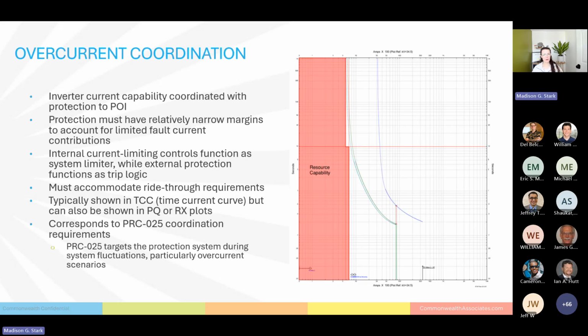The second part of this for inverters is the overcurrent coordination. The big thing that we want to see generally at POI again is that the protection system is not impeding the resource output capability. So we want to see that the inverter can output its full profile, basically, of the current that it can output. If we look at this graph over here on the right, for reference, this red highlighted area is the resource capability for this particular inverter.